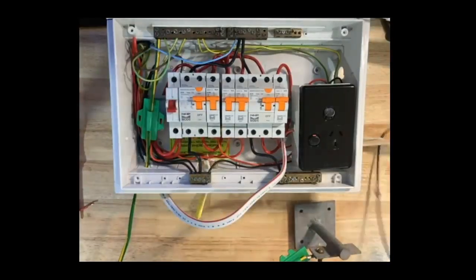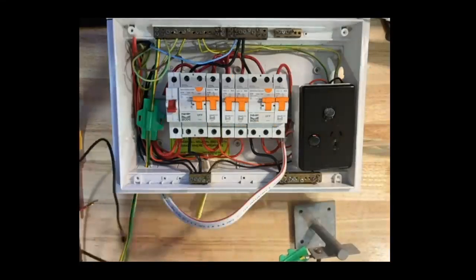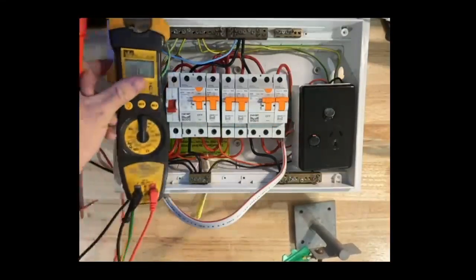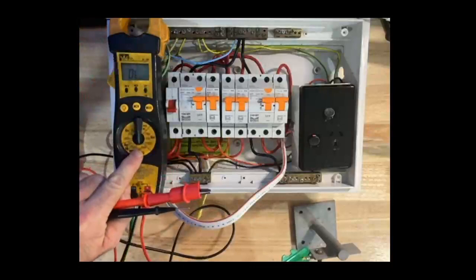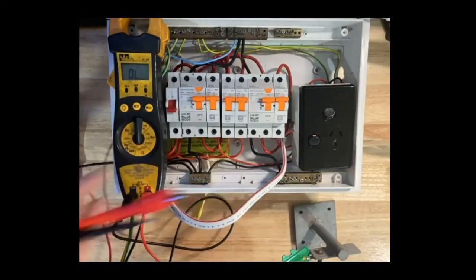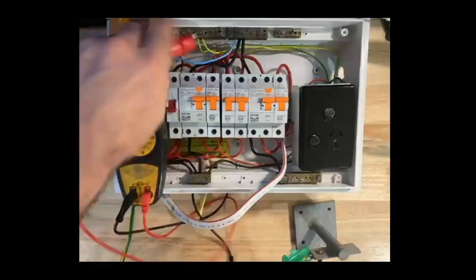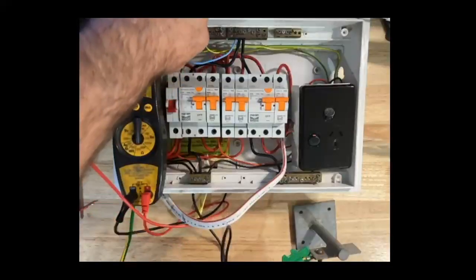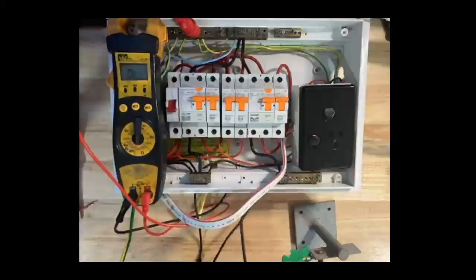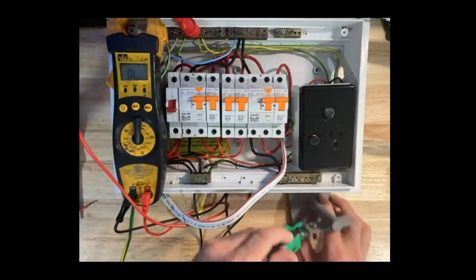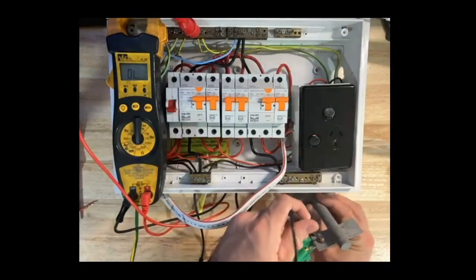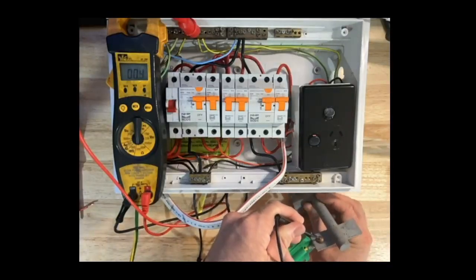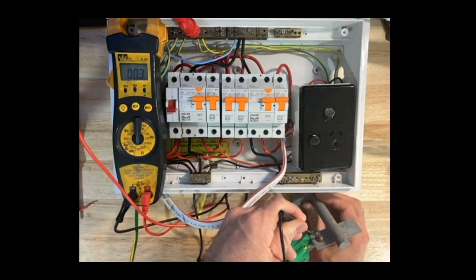But let's start then with our test for our main earth conductor. This is a very simple test. I'm testing for resistance. My meter is set to the ohms scale, and I put one end onto my earth bus bar, and the other end goes to the other side of my main earth conductor out to my earth stake. And we can see the reading there is 0.3 ohms. Perfect.